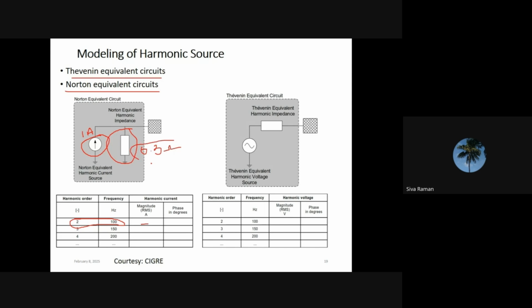So this value, the individual equipment manufacturer needs to provide. Whichever make we are using for the particular site, we have to get it from them. Okay, so we have to consider up to the 50th order minimum. Second order harmonics to 50th order, we have to consider at minimum. If the particular inverter is producing beyond the 50th order, we have to consider those higher order harmonics also in the modeling.